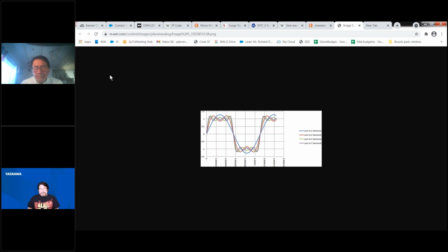In fact, in U.S. Motor's vertical hollow shaft - I think it's actually called their motor suitability guide for VFDs - at the very back of it, almost the last paragraph, there's a statement saying that from now on with their motors you have to make sure you have heaters in them to keep the windings dry.